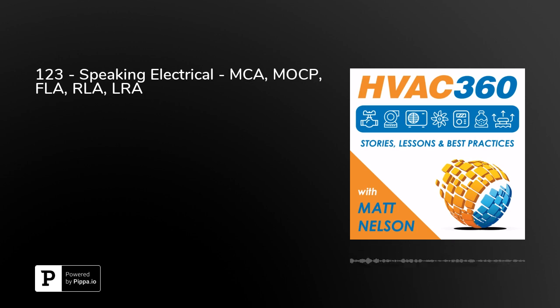And I have heard that if the manufacturer states a maximum fuse rating, and they list a maximum fuse rating when they talk about the MOCP, then the connection must use a fuse. Now, we'll get into that probably a little bit more, and I have one more installment, and that's really talking about electrical connections to equipment and what those different things are. That's going to be another podcast, but suffice it to say that both the MCA and the MOCP can be calculated or given, so you could double check whatever.